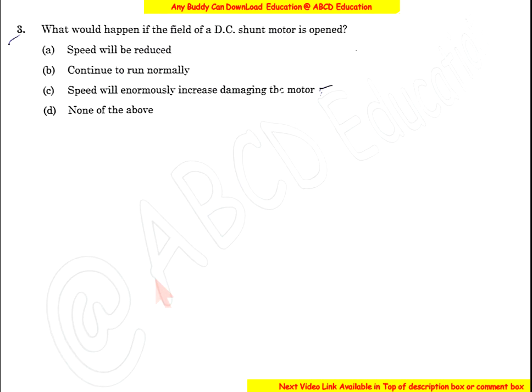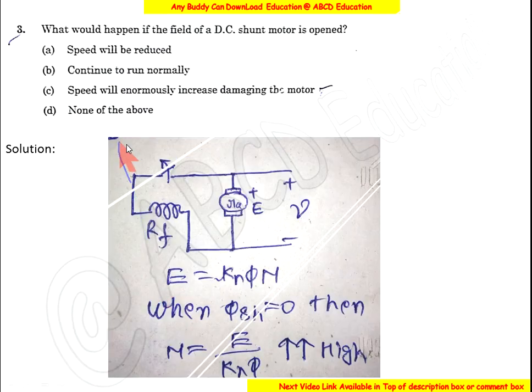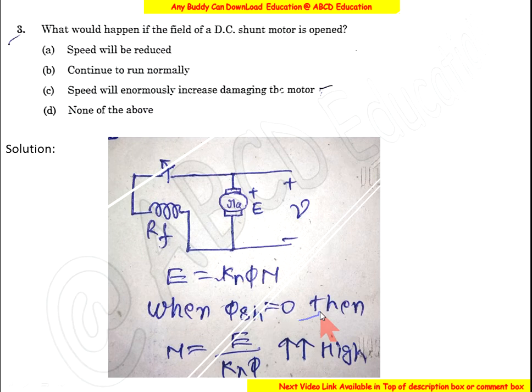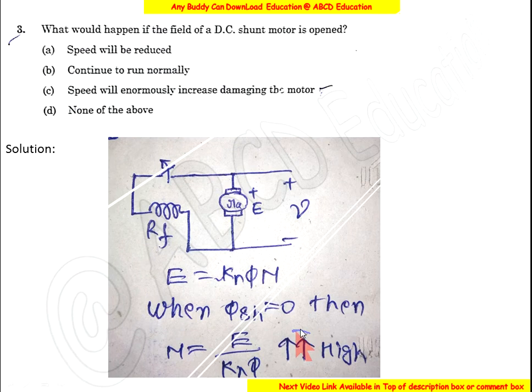Question 3: What would happen if the field of the DC shunt motor is opened? If the shunt field becomes zero, the speed becomes dangerously high because speed is proportional to E/φ, and with φ equal to zero, the speed is E/0. This dangerously high speed will damage the motor. The correct option is C.